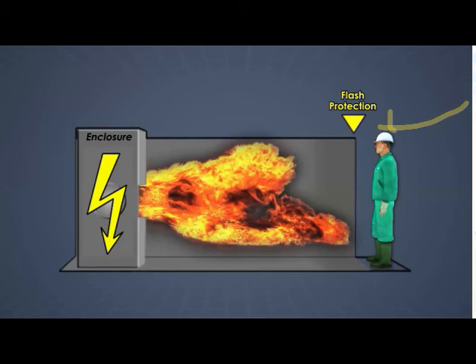A panel can create an electrical arc flash, and the arc flash distance may come up to 3.5 feet, for voltages up to 600 or 660. If it is 1000 or 2000 volts it may extend a little beyond, but in normal working conditions up to 600 volts, it comes to approximately 1 meter. This is the boundary, and whenever we need to enter it, we have to take all protective measures.